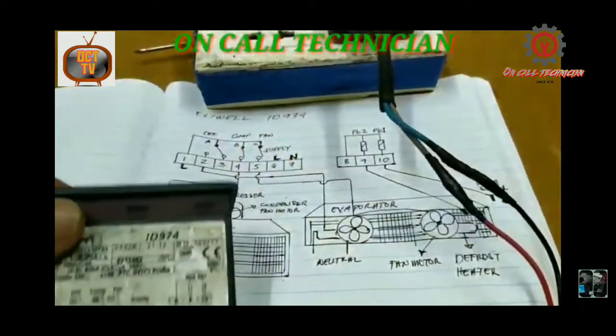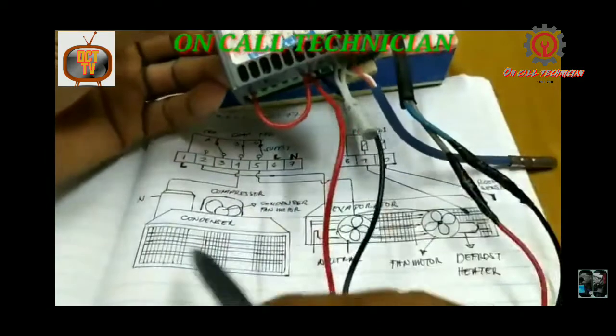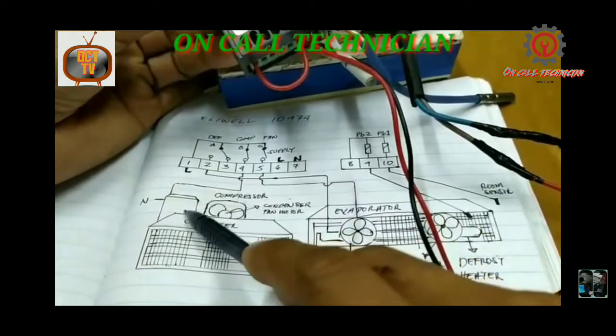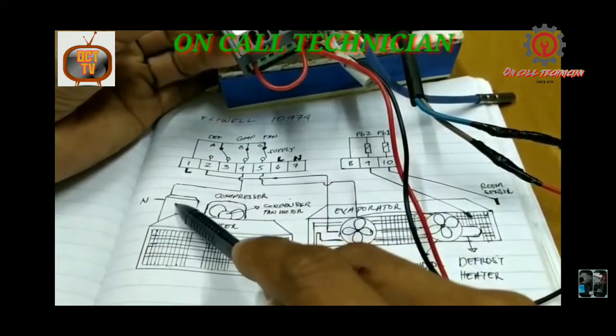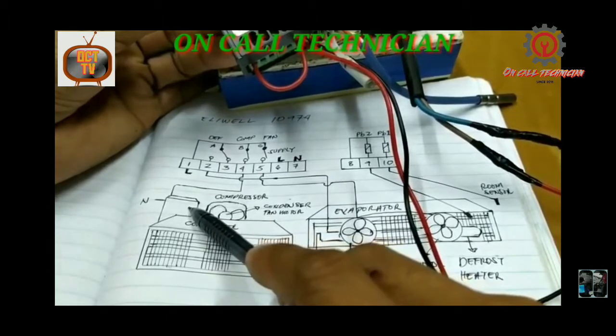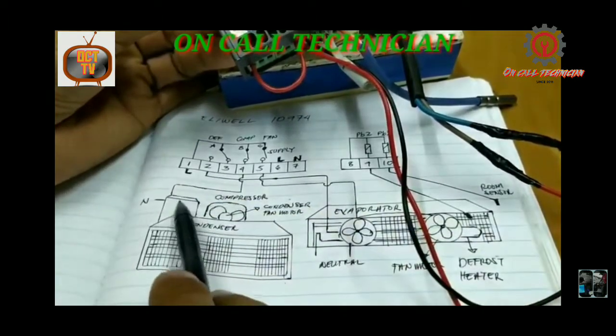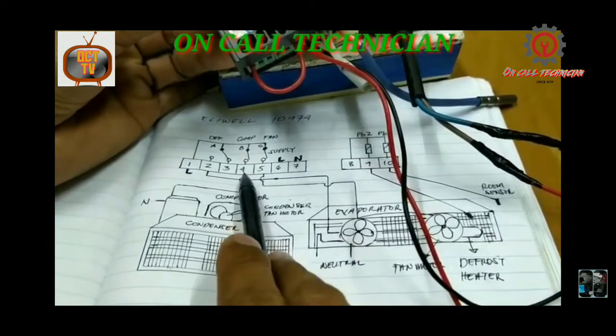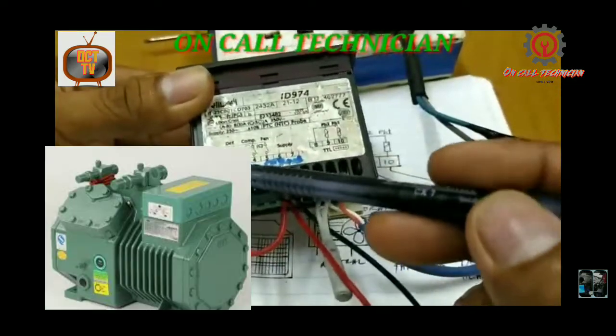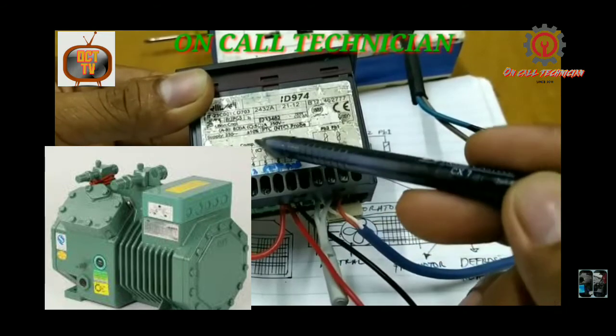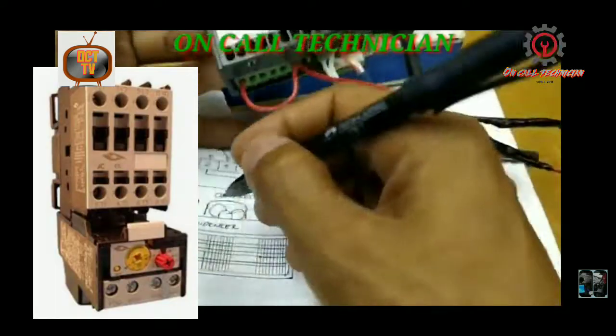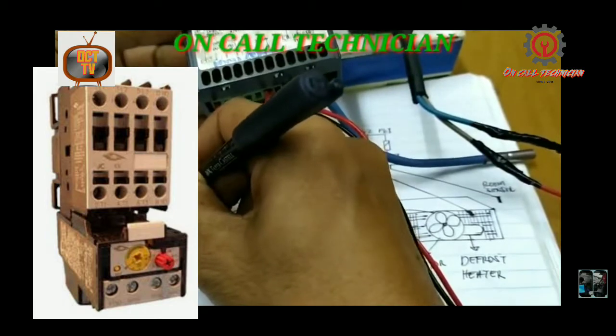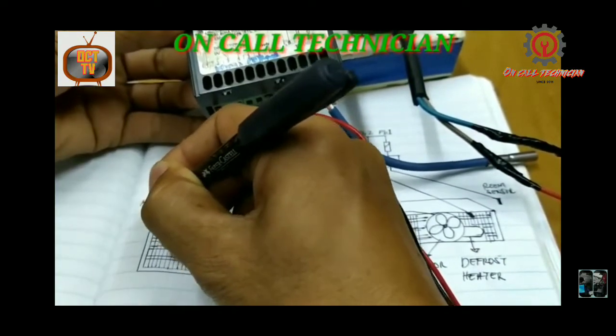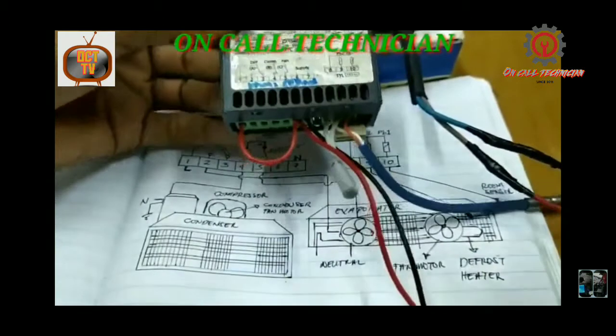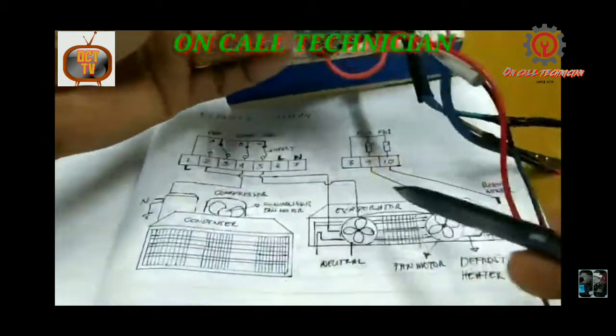Okay, which is live. And number 7 is neutral. This is the compressor and the fan motor for the condenser. So it has a neutral. Just connect the neutral to neutral, and the live going to the control. And remember, guys, if you use it for a compressor, just use a contactor with overload, because our output relay for the control is only 8 ampere.